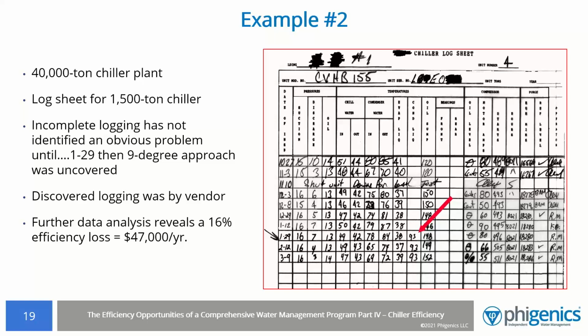And if you look under the temperature columns, under the condenser liquid column, the data is mostly blank. You get down where that red arrow is, and they finally entered a number for the saturated refrigerant temp in the condenser. You then back up and look at the temperature of the water leaving the condenser at 84. That's about a 9-degree approach. That's about a 16% efficiency hit on this machine, 1,500-ton machine. And that alone is about a $47,000 per year waste in energy. So they had a fair amount of data. They got complete data later in the program, but they didn't do the analysis necessary to tell them that they had a very significant issue.